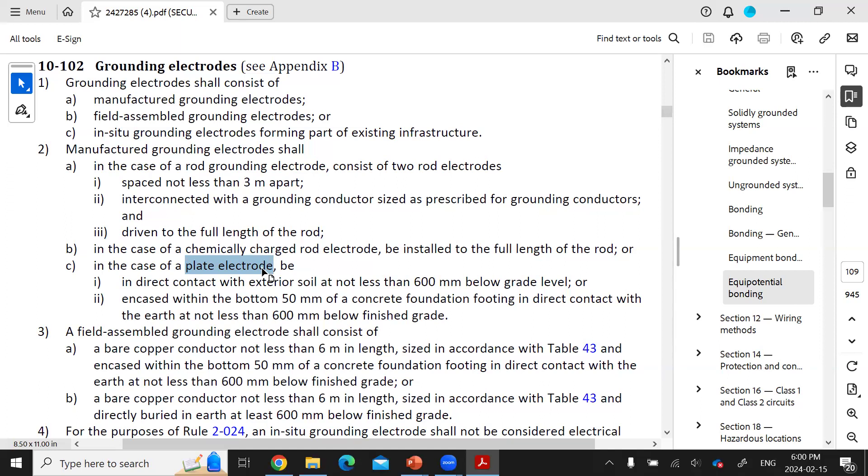Sub-rule 3 talks about a field-assembled grounding electrode that you might make out of some material that you have on hand. If you make a field-assembled grounding electrode, you will probably use bare copper conductor that is encased in a concrete footing in direct contact with the earth. The bare conductor has to be sized in accordance with Table 43 and it can be no less than 6 meters in length and has to be buried at least 600 millimeters below the surface.